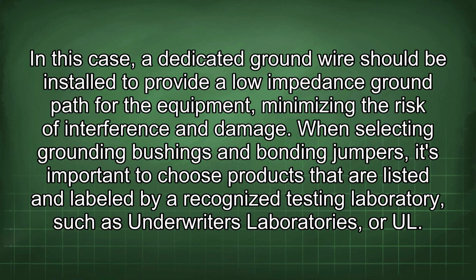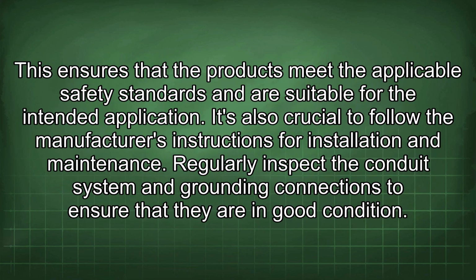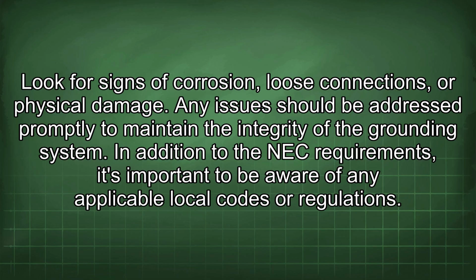When selecting grounding bushings and bonding jumpers, it's important to choose products that are listed and labeled by a recognized testing laboratory such as Underwriters Laboratories, or UL. This ensures that the products meet the applicable safety standards and are suitable for the intended application. It's also crucial to follow the manufacturer's instructions for installation and maintenance. Regularly inspect the conduit system and grounding connections to ensure that they are in good condition. Look for signs of corrosion, loose connections, or physical damage. Any issues should be addressed promptly to maintain the integrity of the grounding system. In addition to the NEC requirements, it's important to be aware of any applicable local codes or regulations.